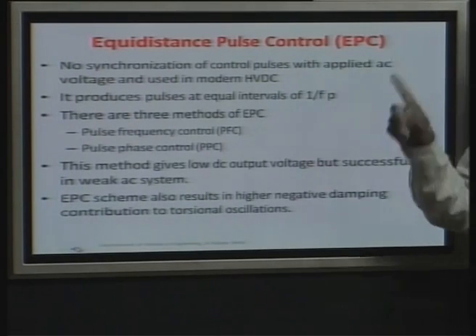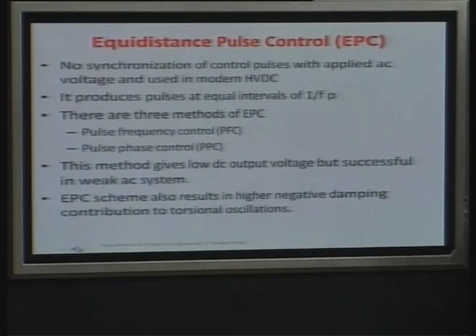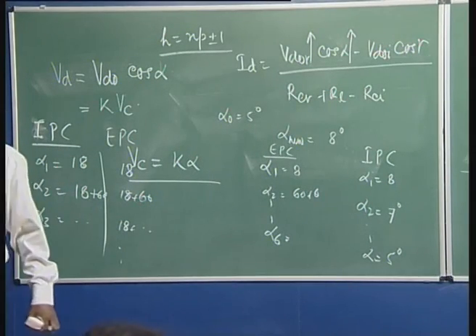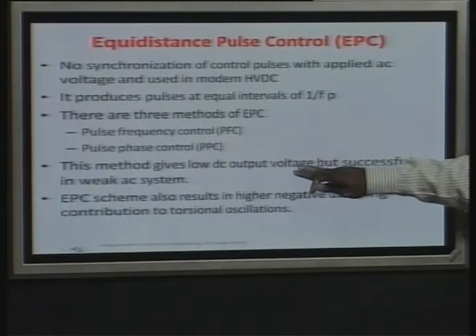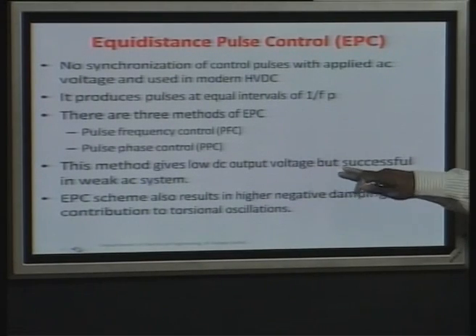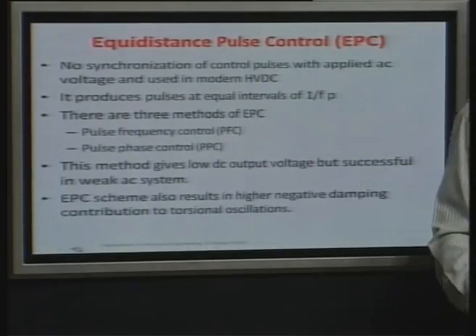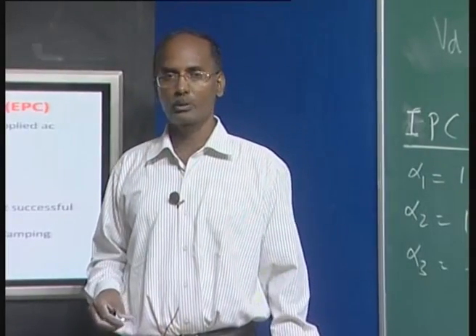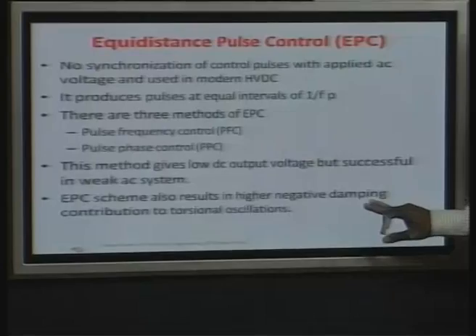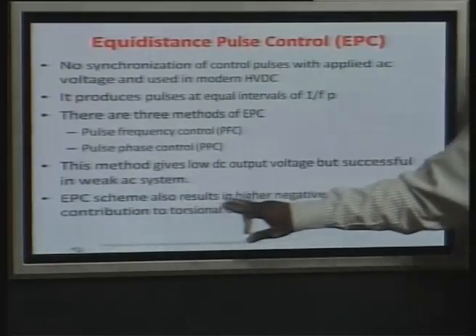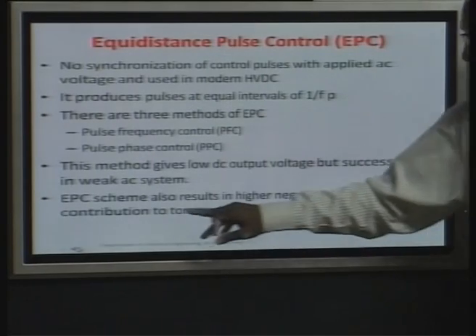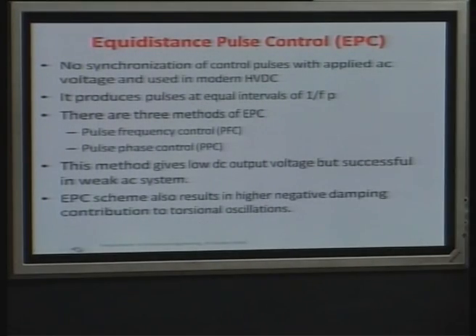This method gives lower DC output voltage but is successful even in weak AC systems — instability problems are avoided. However, EPC schemes also result in higher negative damping contribution, especially to torsional oscillations. Torsional oscillation especially arises when having thermal power plants, where harmonics entering the mechanical system cause oscillations in torsional torque due to matching frequency — sometimes called sub-synchronous resonance in the AC system.